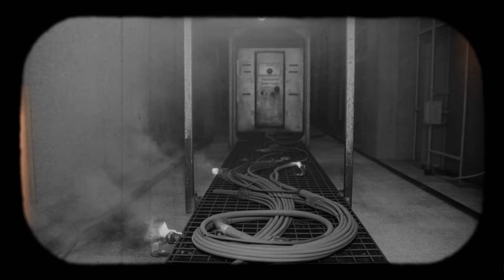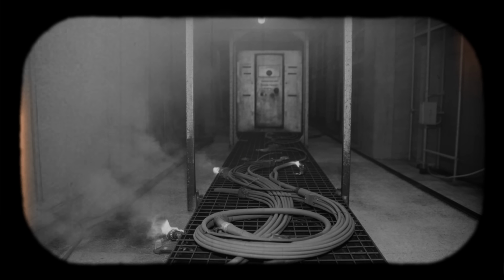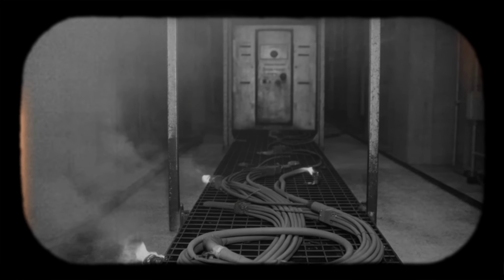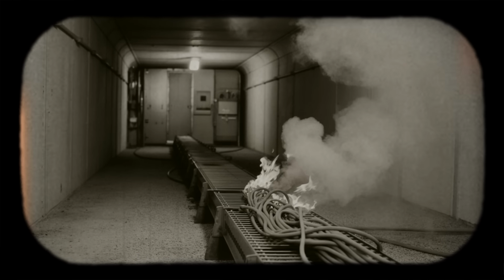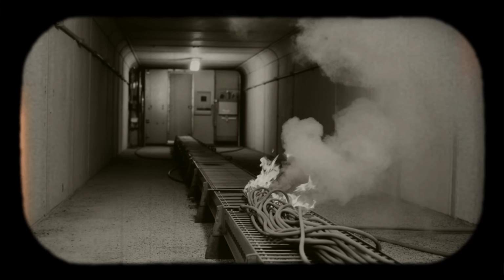For 7.5 minutes, high current heating stressed roughly 120 meters of 6 kV cable. Copper conductors, insulation, protective jacket, all heating beyond design limits. Eventually, someone manually tripped the defective 220 kV breaker, but by then thermal damage was done.